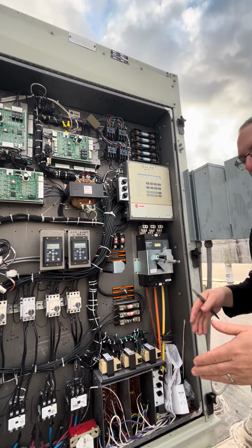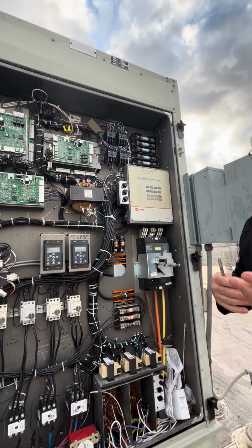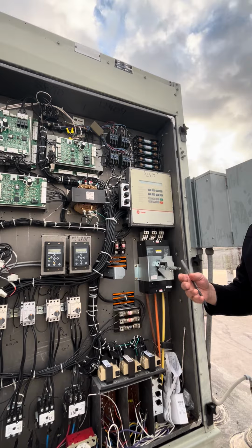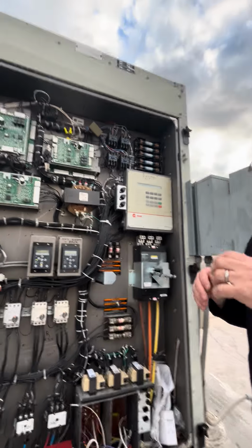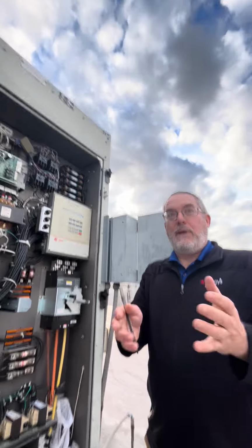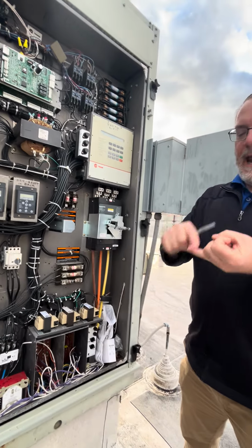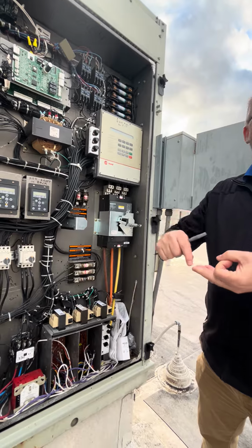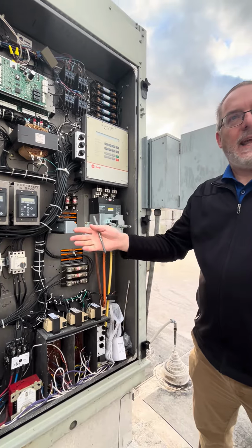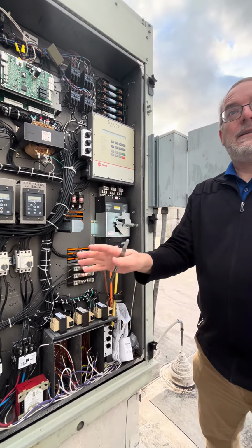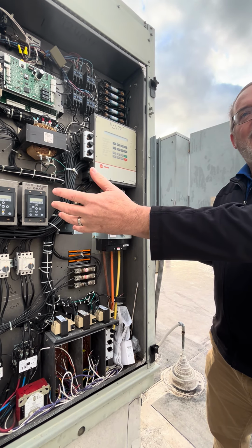When this store was opened, this isn't that old a store, we probably had 105 watt incandescent spotlights, a lot of heat load. Yeah, you said a lot's changed on the heat load. So these units, and it doesn't matter if it's central plant. I've been with Macy's 30 years. In April it will be 30. And I've seen us go from halogen and quartz and 150 watt spots down to 120, down to 105, all now LED, and now you've got the case lines, you've got BTUs of heat in the building, but you've taken so many out. But we haven't downsized this equipment.